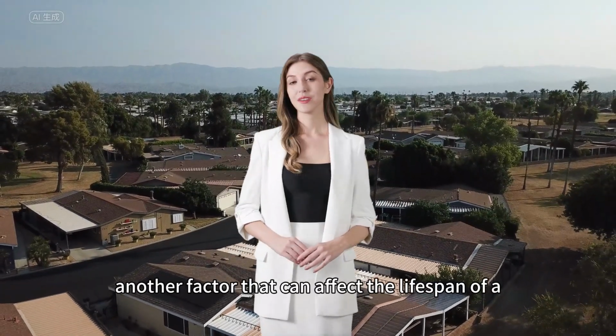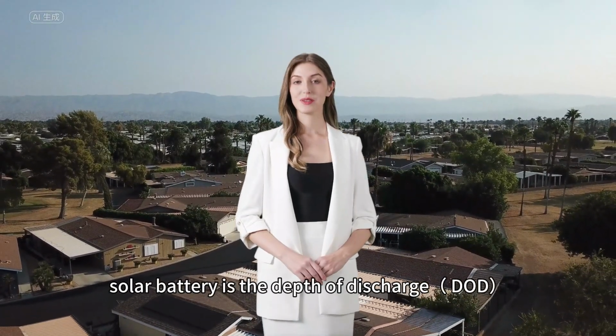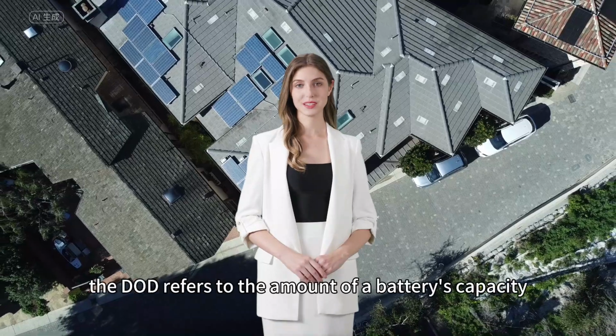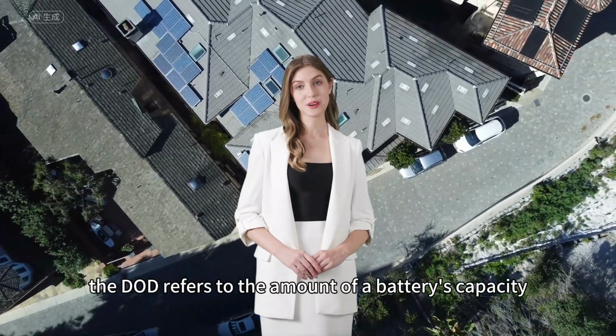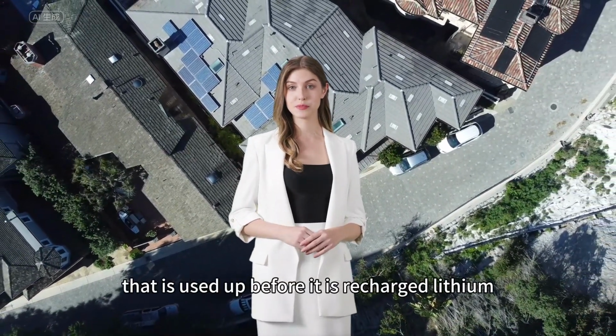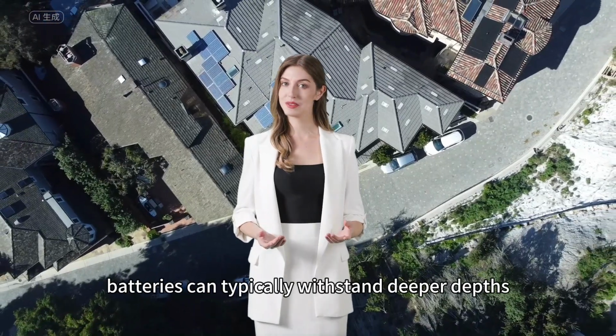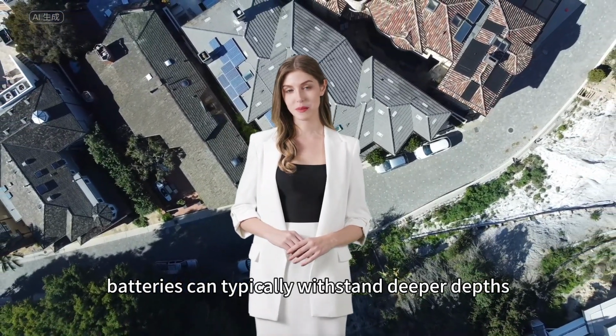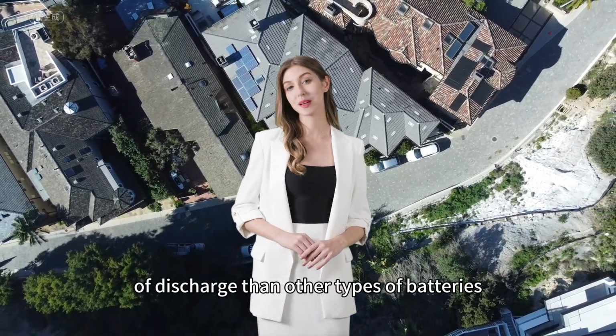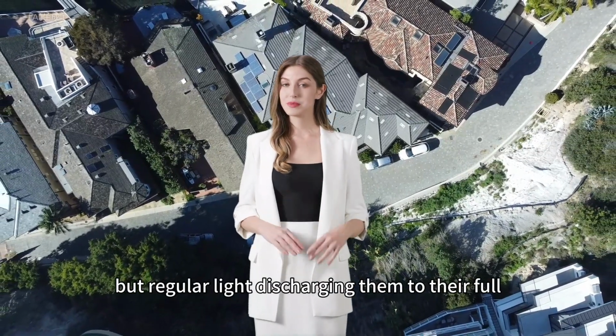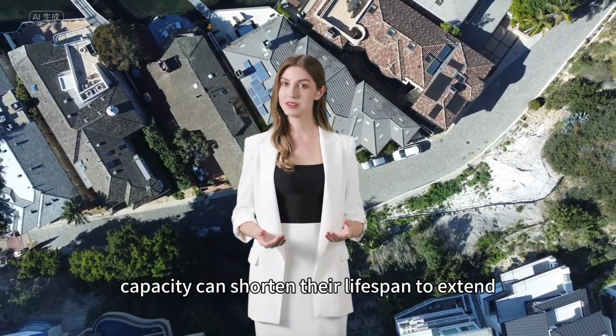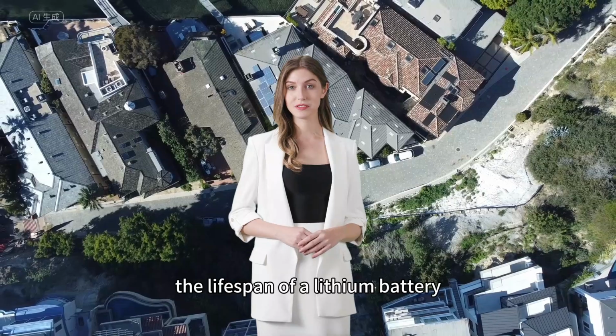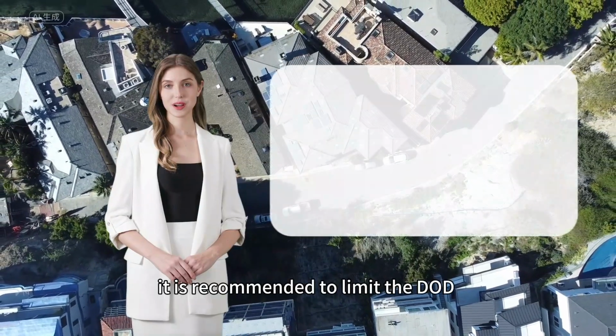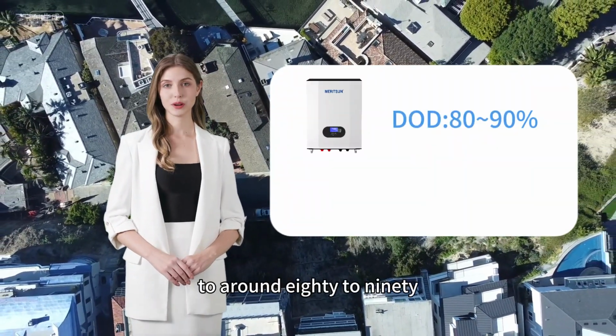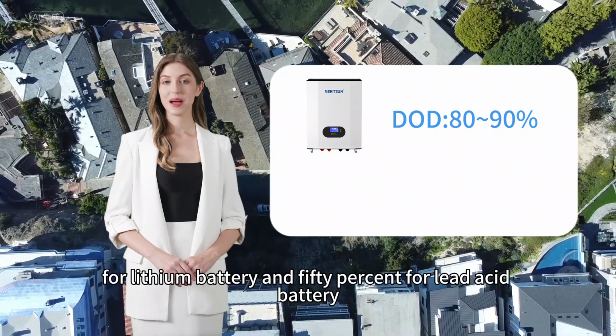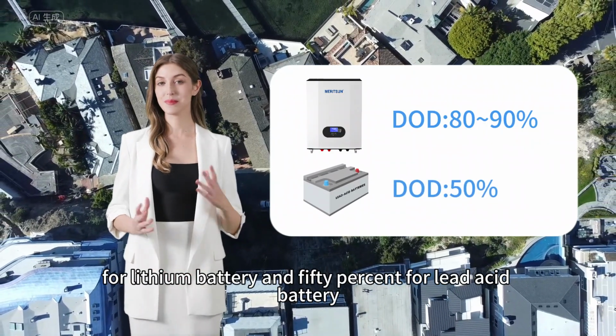Another factor that can affect the lifespan of a solar battery is the depth of discharge (DOD). The DOD refers to the amount of a battery's capacity that is used up before it is recharged. Lithium batteries can typically withstand deeper depths of discharge than other types of batteries, but regularly discharging them to their full capacity can shorten their lifespan. To extend the lifespan of a solar lithium battery, it is recommended to limit the DOD to around 80 to 90% for lithium battery and 50% for lead-acid battery.